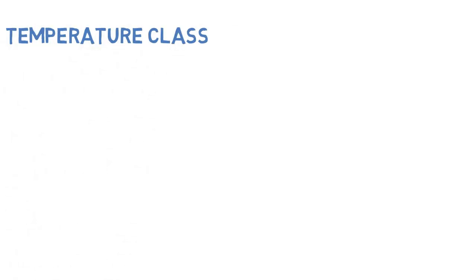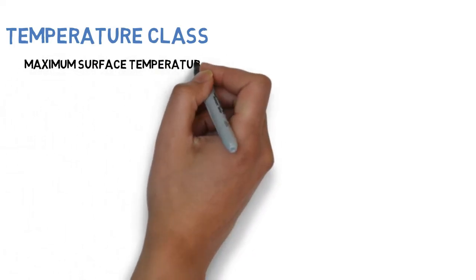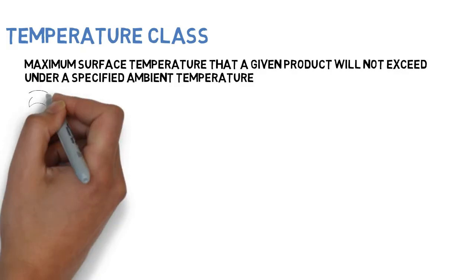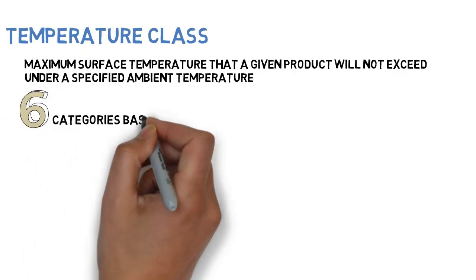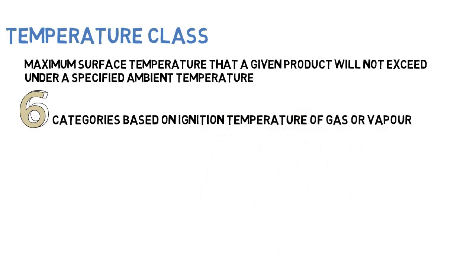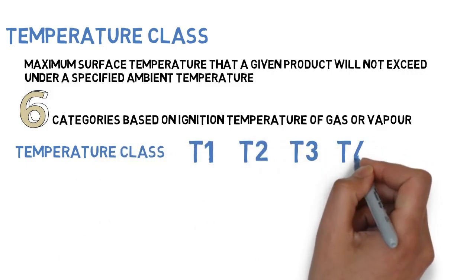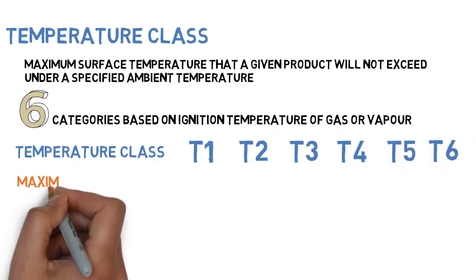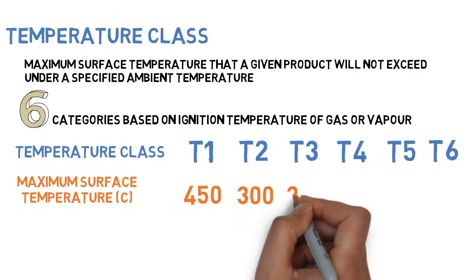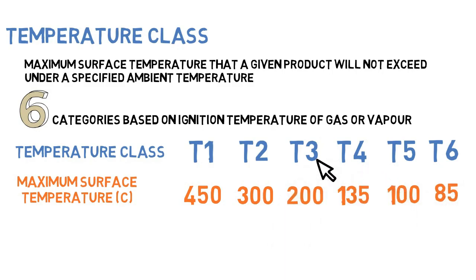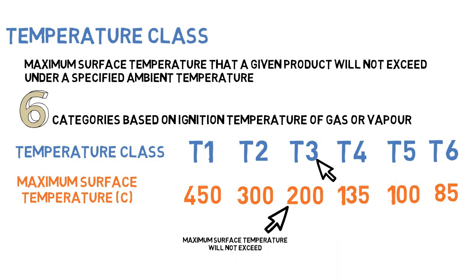Temperature class denotes the maximum surface temperature that a given product will not exceed under a specified ambient temperature. Temperature class is classified into six categories based on ignition temperature of gas or vapor: T1, T2, T3, T4, T5, and T6. Accordingly, the maximum surface temperature is provided. For example, a product with a T code of T3 means that its maximum surface temperature will not exceed 200 degrees Celsius, provided it is operated at an ambient temperature defined by the manufacturer.